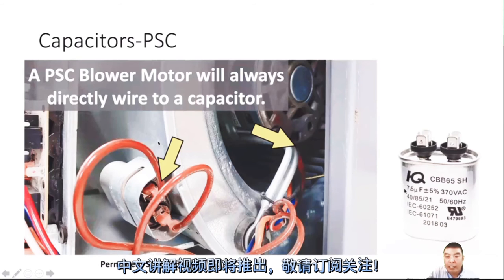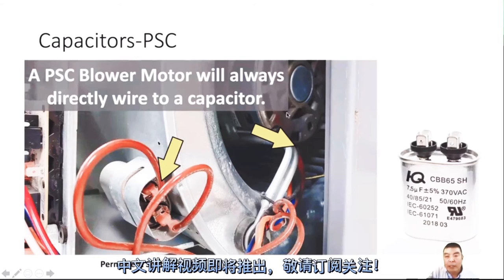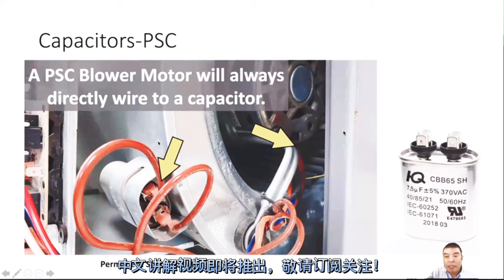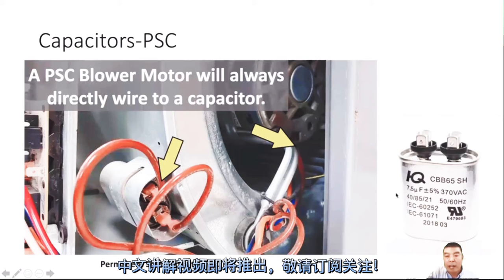For furnace capacitors, normally they are 7.5, 5, or 10 microfarad. We can see here this one is 7.5. This number depends on the horsepower of the motor. If yours is a one-horsepower motor, you may need a 7.5 or 10 microfarad. If it's only half horsepower, you may only need a 5 microfarad.